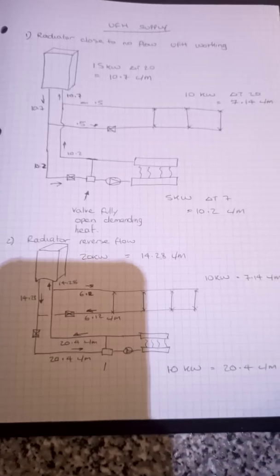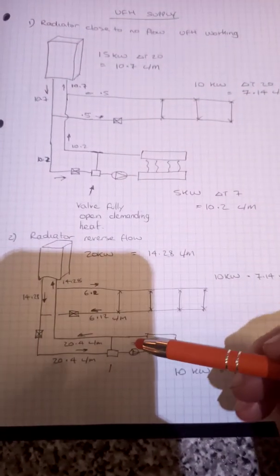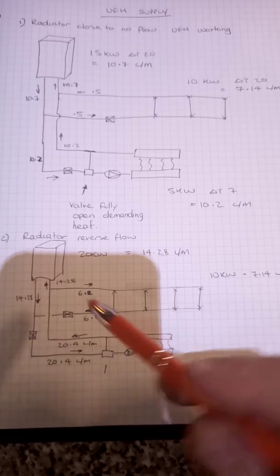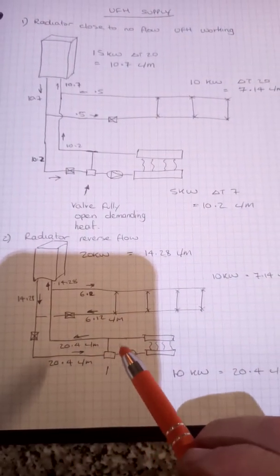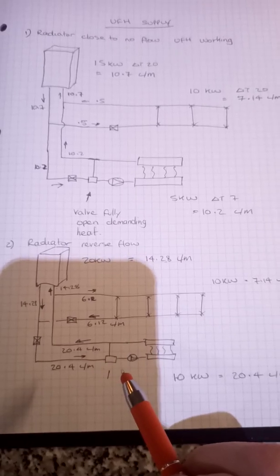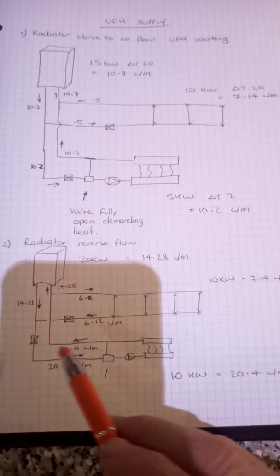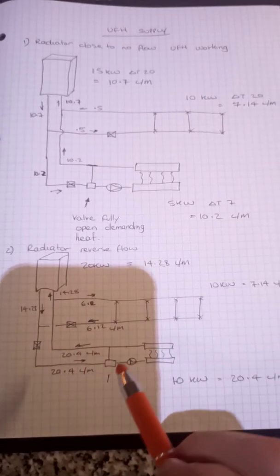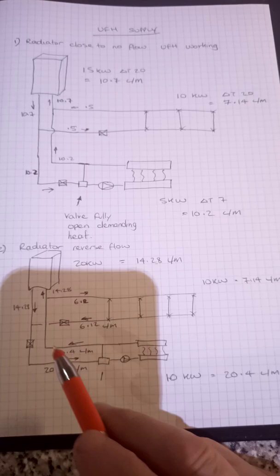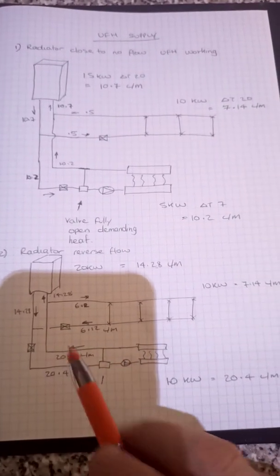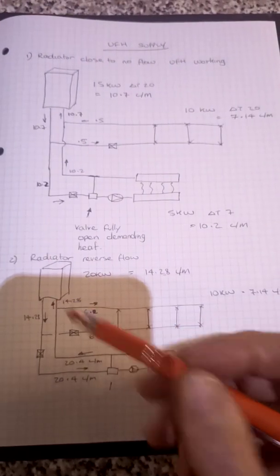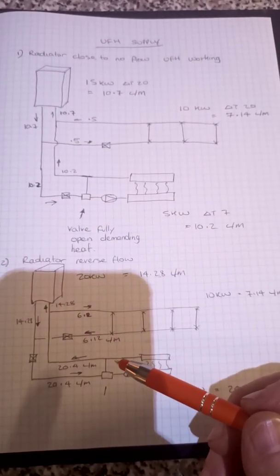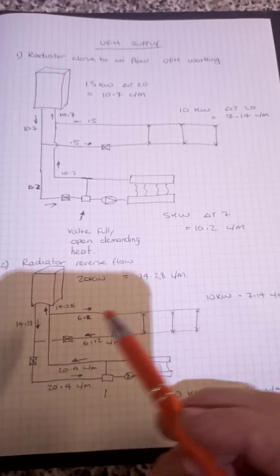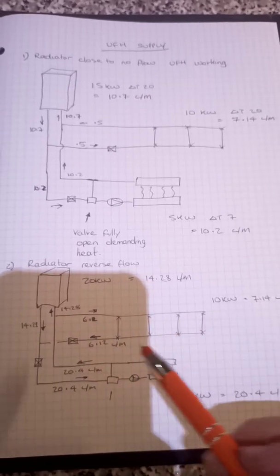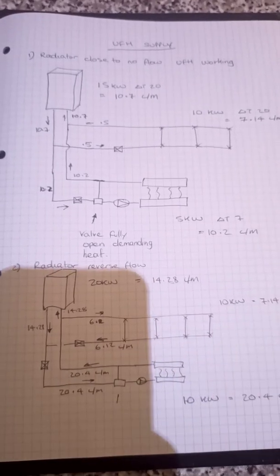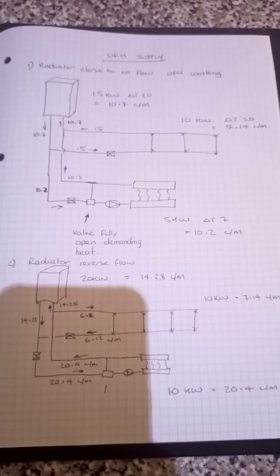So just another thing I'd quickly add. A lot of people are being told to install close coupled T's after the radiator circuit and at the manifold. This is a no-no. Don't do this. You're going to create a full flow bypass. If you put a balancing valve in it to stop it being a full flow bypass, you've still got a bypass. You've still got an open bypass. And this is not the same as hydraulic separation. That bypass will simply drop the available pump head from the radiator circuit and will cause an underflow in the radiator circuit. Now, you might not notice these things. The symptoms might not be obvious enough, but they are there.